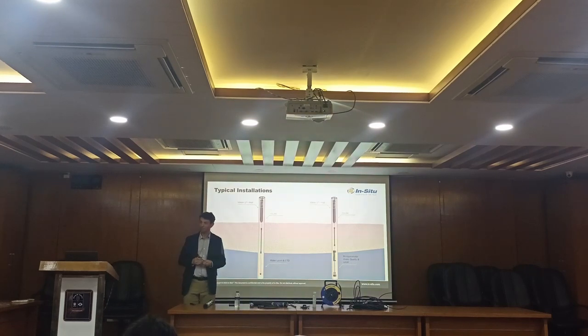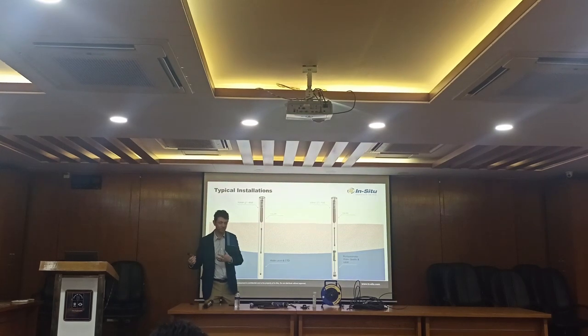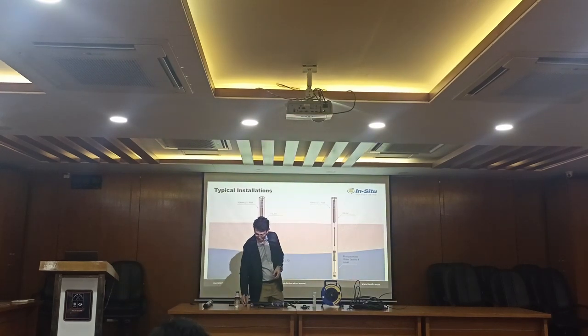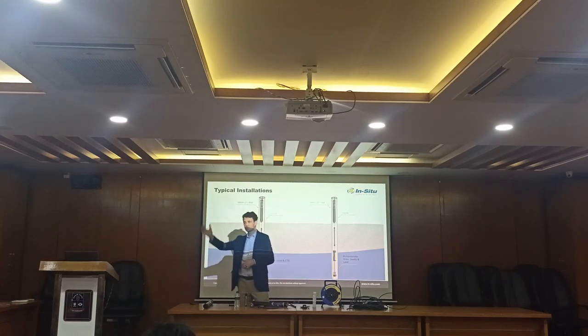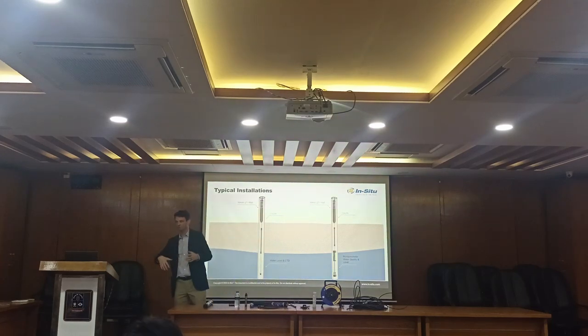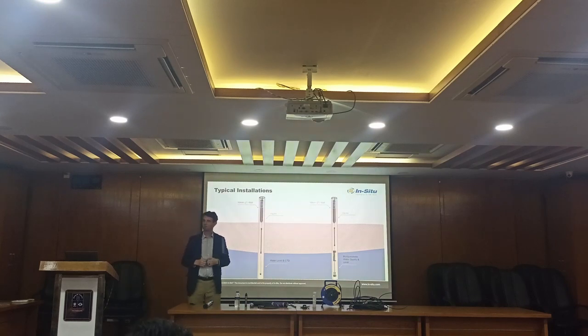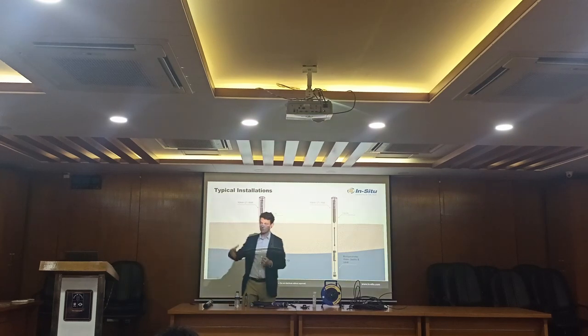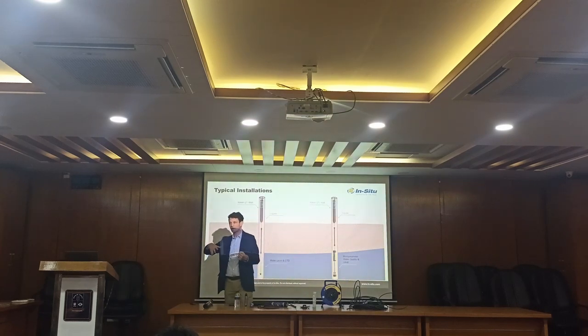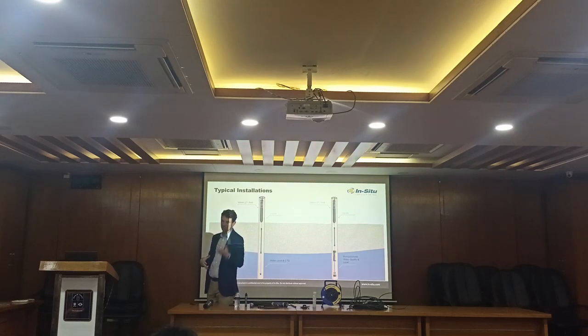These aren't great for that, separate story. But if you have really hot water, what about moving between things? What if I'm dealing with a coastal environment where there's diurnal fluctuations? What if I'm dealing with a river where it's sunny, it's dark, temperature changes? What if I'm dealing with groundwater where there's a discharge from an industry putting out hot water into the ground, and then it changes? My water level, if it's not calibrated across the whole temperature and pressure range, the water level reading will be inaccurate. And that's the critical part.